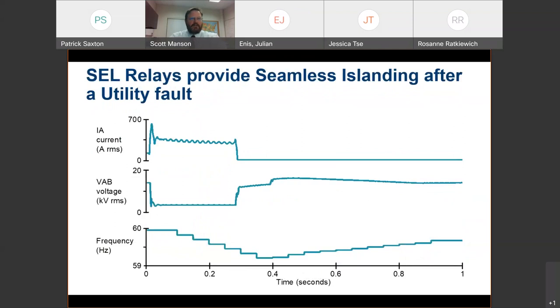So here's that same event put into RMS values, much easier for the eye to detect. Here on the top axis is current at the point of coupling. This is the microgrid back feeding the fault. You can see the current surge, the transient reactance, the generators, in the subtransient reactance. And then you see over time the current levels off and then eventually extinguishes.